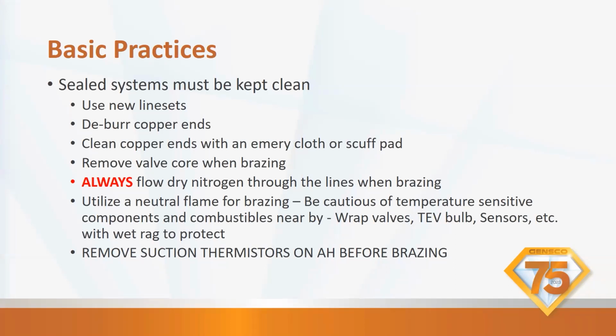Make sure that you're using a neutral flame for brazing. Be cautious of the temperature sensitive components and combustibles. Wrap valves, wrap the TXV bulb, or remove it. Sensors, wrap everything with a wet rag. Now on air handlers, take the suction thermistor off before brazing. If you don't do that, you will melt it. You will cause damage to it. And that makes your EEV not work correctly. That makes your charging incorrect. So be very careful with those suction thermistors.